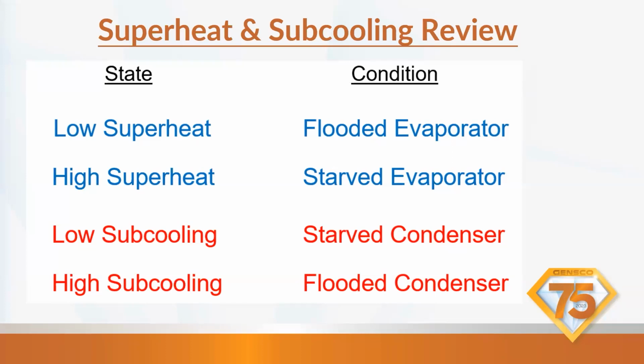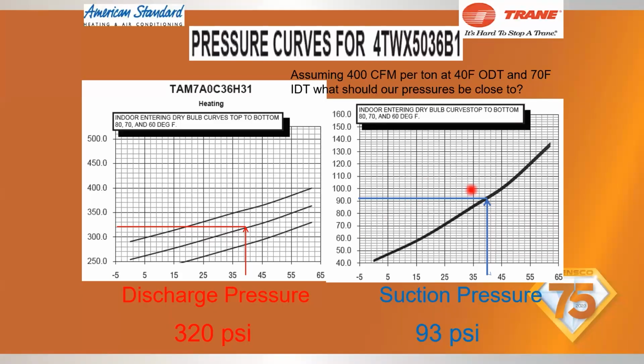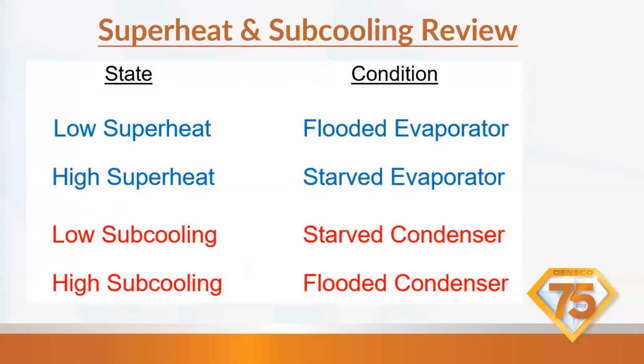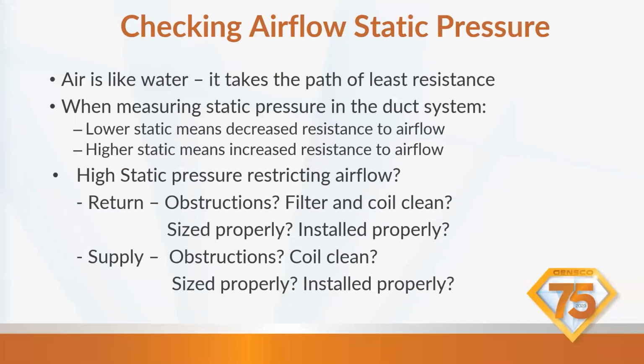and then get your pressures within your pressure curves. They could get tricky where you have high head pressure and low suction pressure. This could be airflow related. So that's why we're going into checking airflow and static pressure too. And airflow with the TXVs also, airflow affects everything.